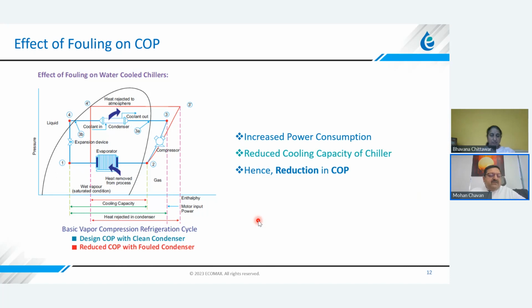This is a simple graph which all of us, being engineers, have studied in college. It's a pressure enthalpy chart. Now I'll try to explain here how scaling or fouling impacts the efficiency of the chiller. Now this 1 to 2 is heat removed from the process or from the space. That is called the evaporator. 2 to 3 is the compressor. The gas will be compressed by the compressor to point number 3. 3 to 4 is heat rejected to atmosphere, that is maybe the condenser, right? And 4 to 1 is expansion. So this is your standard refrigeration cycle.